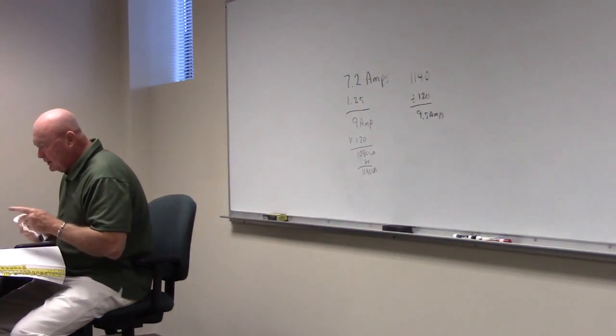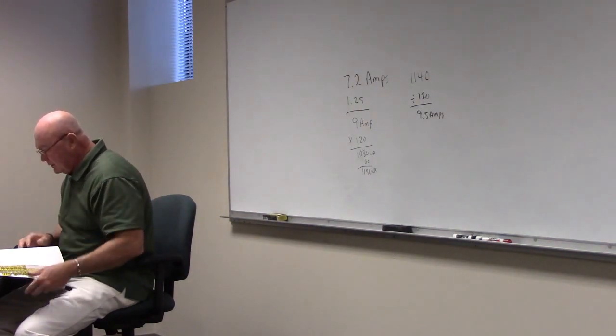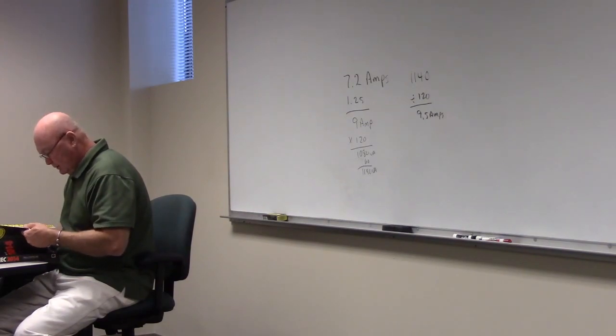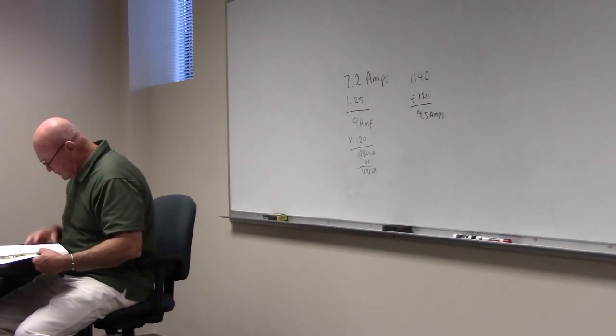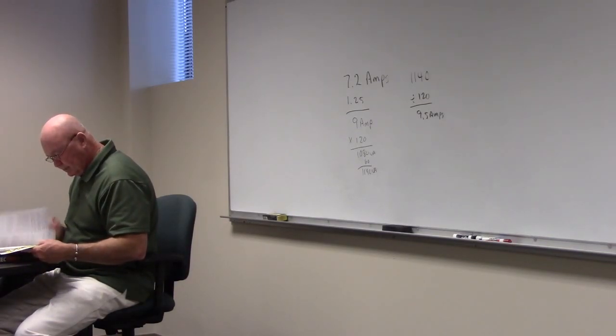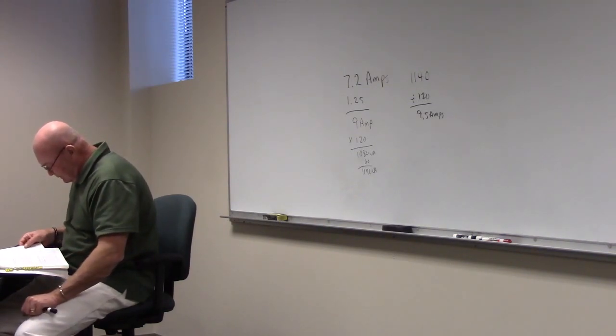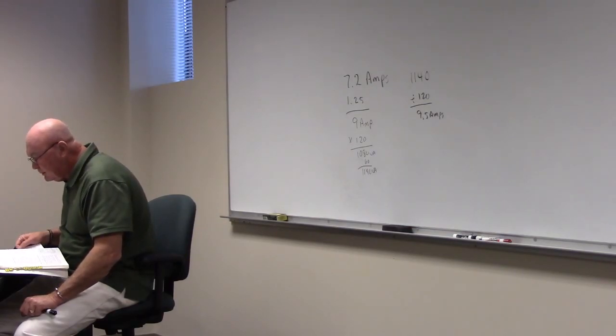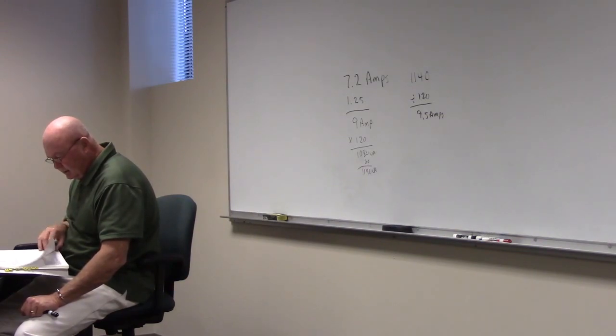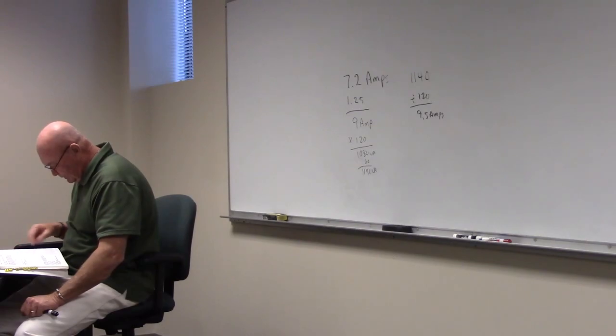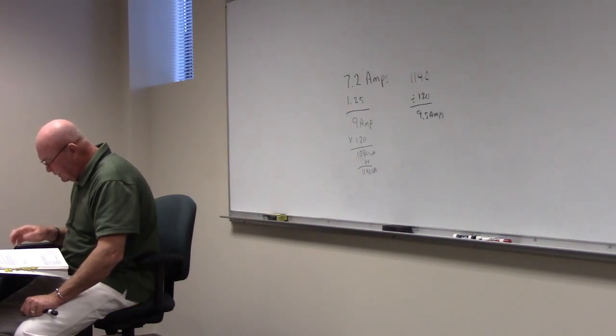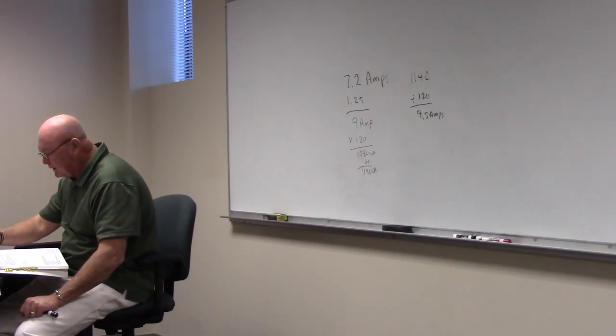Step 2 says check the NEC 230.42(A) for the minimum size service entrance conductor. So we better go there. 240. But we ain't got much right there. 230, I'm sorry, I said 240. I knew that didn't look right. The ampacity of service entrance conductors shall not be less than either 230.42(A)(1), (A)(2), (A)(3), will be determined. Maximum current of the load will be the sum of the non-continuous plus the continuous load, that's number 1. Sum of the non-continuous plus the continuous load after application, number 2, is what we just did. And so on and so forth, okay? So I don't see anything there that hurts us.